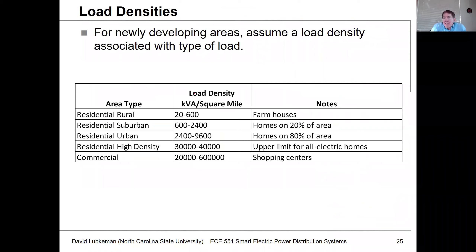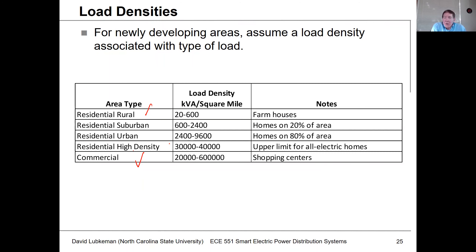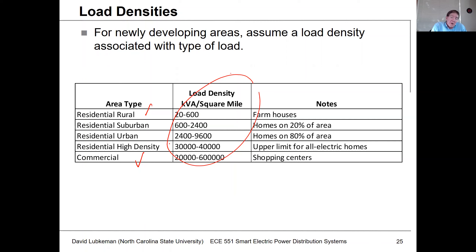For newly developed areas, you don't even have any load out there. You need to know at least something about whether this is going to be residential load or commercial load. Utilities have certain indices about what would be the amount of KVA load per square mile that they could use for starting to build models. You may be starting with something as rough as just a load density per square mile, and you've got to work from there to do your analysis.